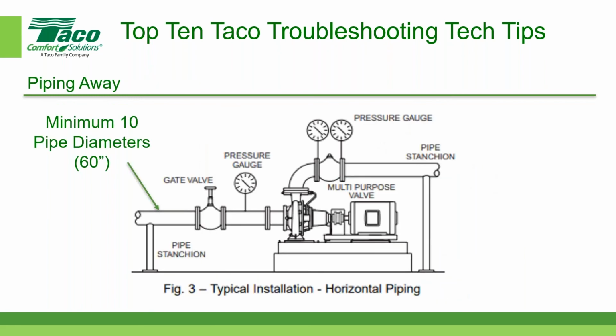Okay. What we would like for a typical installation, we'd love to have a minimum of 10 pipe diameters at the inlet. In this particular case, it happens to be a 6-inch pipe, so we'd like to have 60 inches. And I can hear people screaming up and down right now, saying, "Oh, we can never get that." Which is why it's nice to have an end suction diffuser. If you can't get the minimum pipe diameters and you need to make an elbow, it's nice to have an end suction diffuser. They do a reasonably good job, within their own limitations, of straightening out the flow and providing reasonable entrance conditions. But keep in mind that when the pump is tested at the factory for the actual performance data that's published, it's done with a minimum of 10 pipe diameters at the inlet.